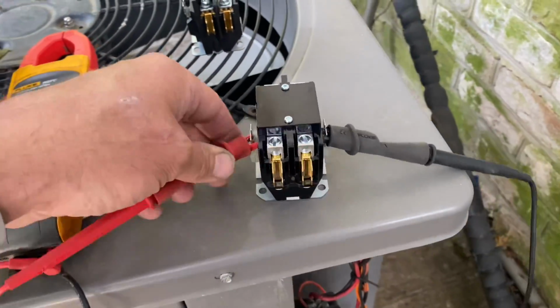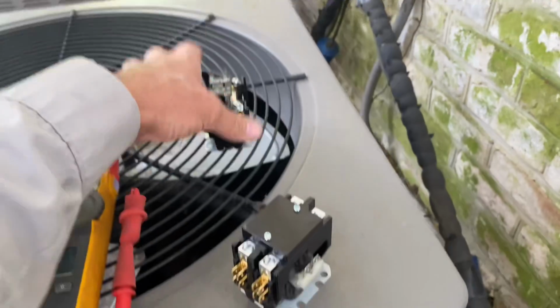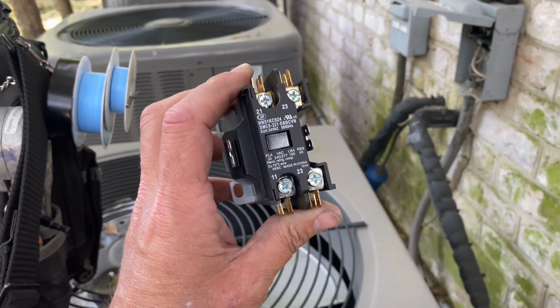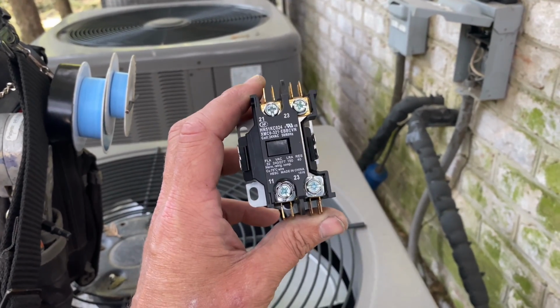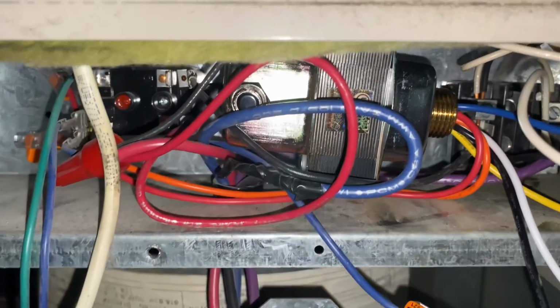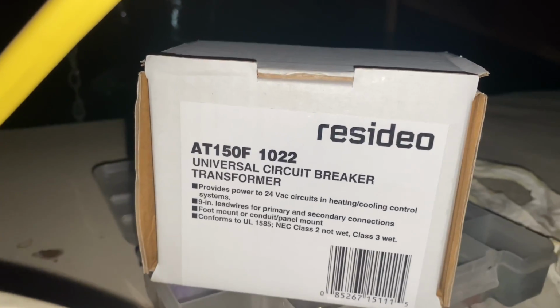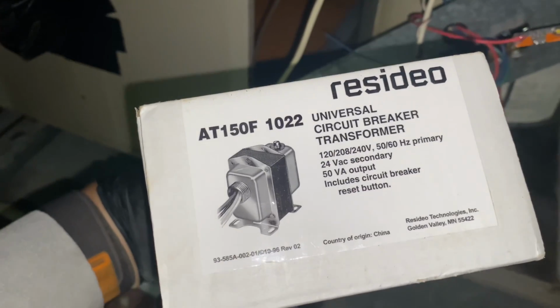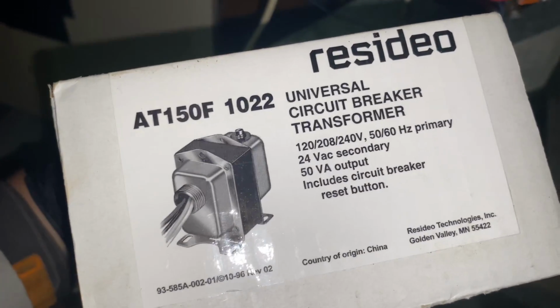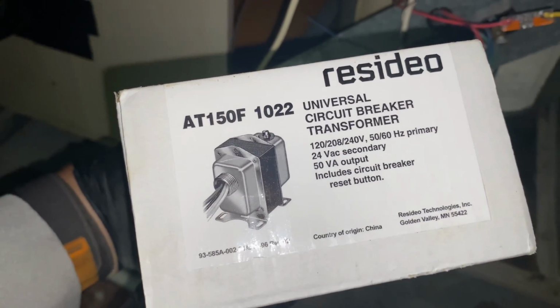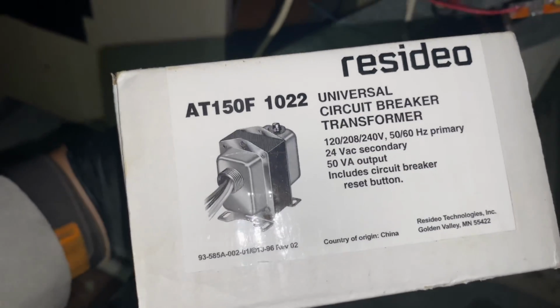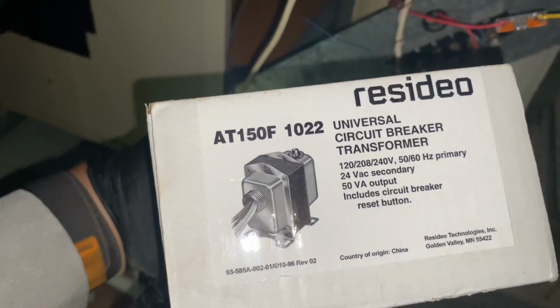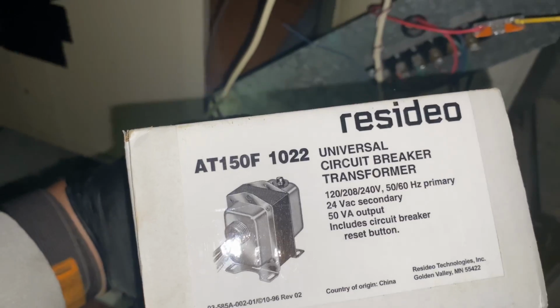Now, since this is a good coil and this is a bad coil, I've now determined what blew up that transformer. All right, so I have a new transformer installed. That's the Honeywell AT150F 1022. This is for 240, 120, 208, 240, and it has as a primary, and 24 volts as secondary, at 50 VA. So this is a 24 volt transformer that will accept incoming line voltage of 110, 208, or 240.